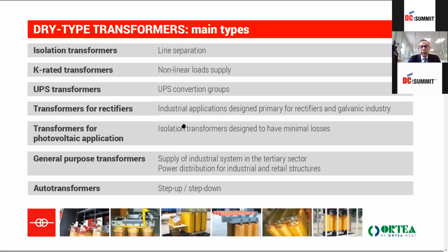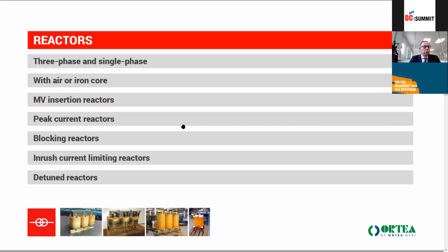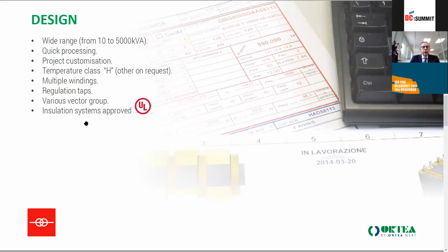So these are very easy systems. So most of the time, the reactors can be single or three phase, can be on air or with iron core, medium voltage or low voltage, peak reactor, blocking reactor, inrush current limiting systems, and detuned reactor for power factor correction systems. We are a certified company, so we have an insulation system certified UL on request, which is not always there because it depends on the final destination or the specification of the project. We do reach 5,000 kVA. We do have a very high possibility and skill to design special units according to specs. We do use aluminium or copper winding system according to the customer needs and the different vector groups.